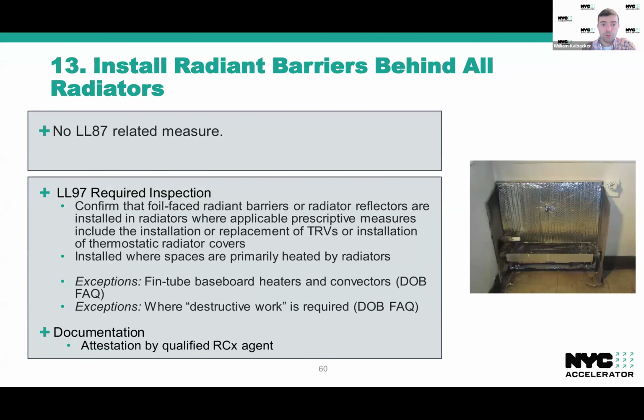There is no direct 87 measure here, so it's a unique component of the prescriptive path and those measures. In terms of the inspection, basically an RCX agent needs to confirm that the foil-faced barriers are installed in radiators where they're applicable, again, where the TRVs or radiator covers are installed. And it needs to be installed in places where the primary heating is provided by radiators and not some other form of heater like electric resistance, for example.